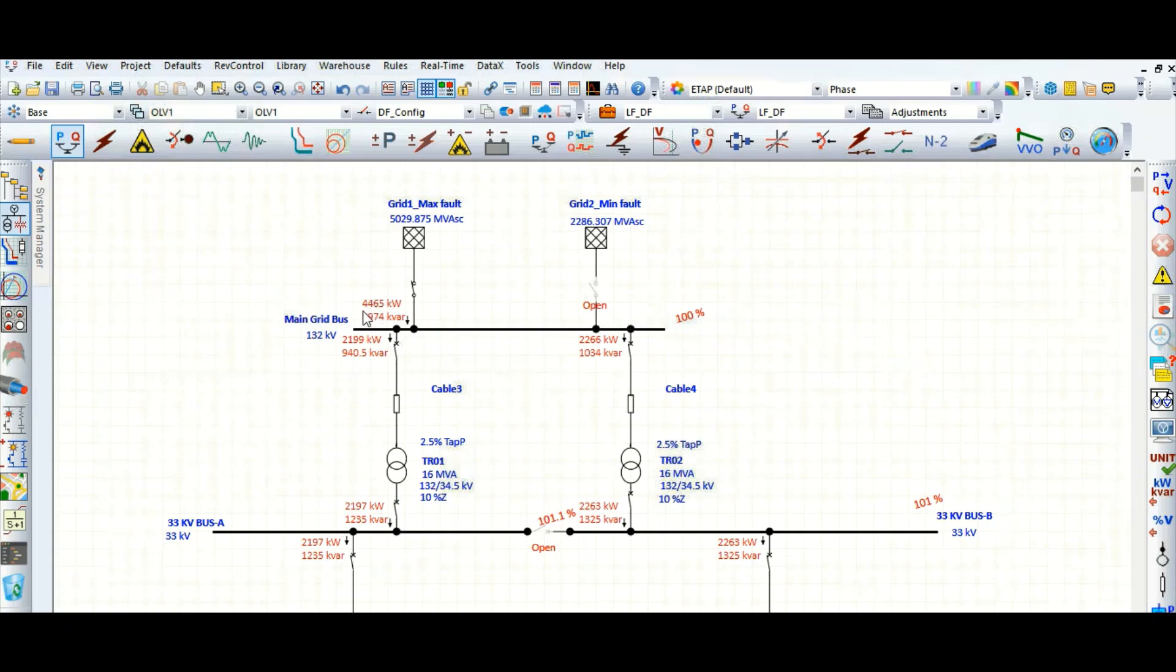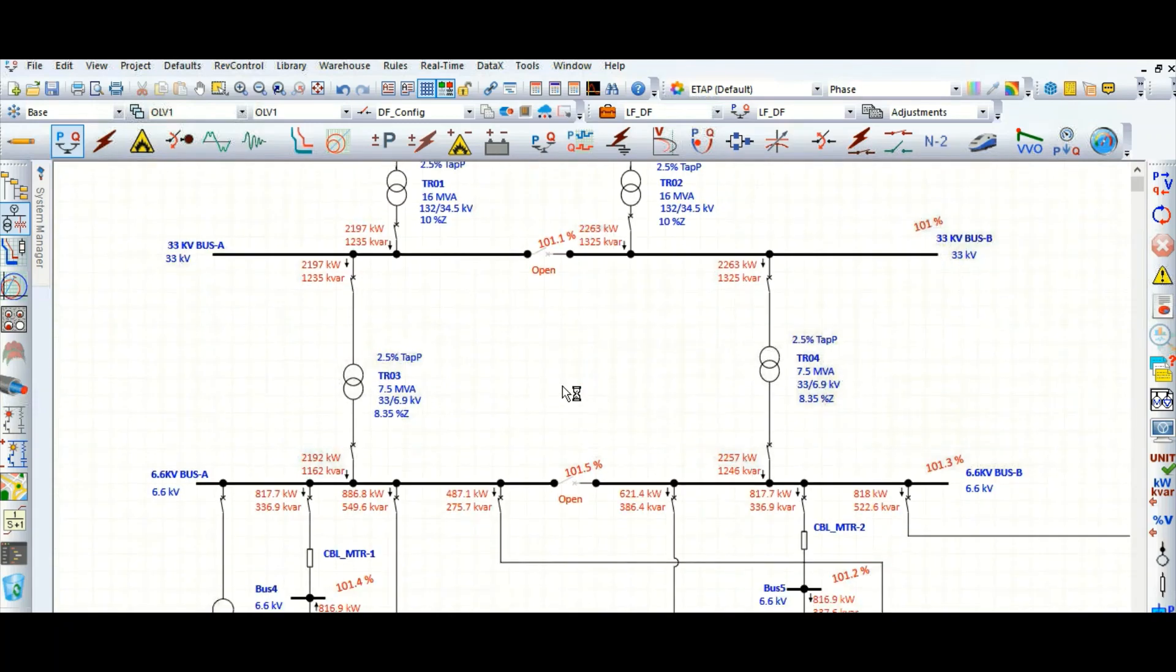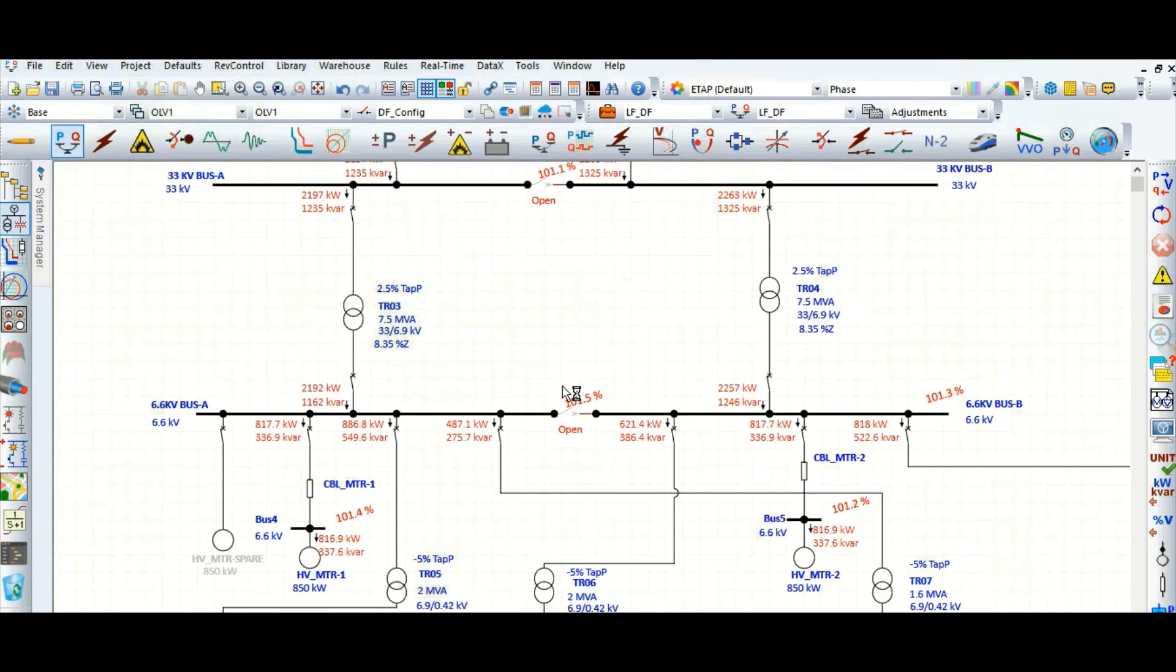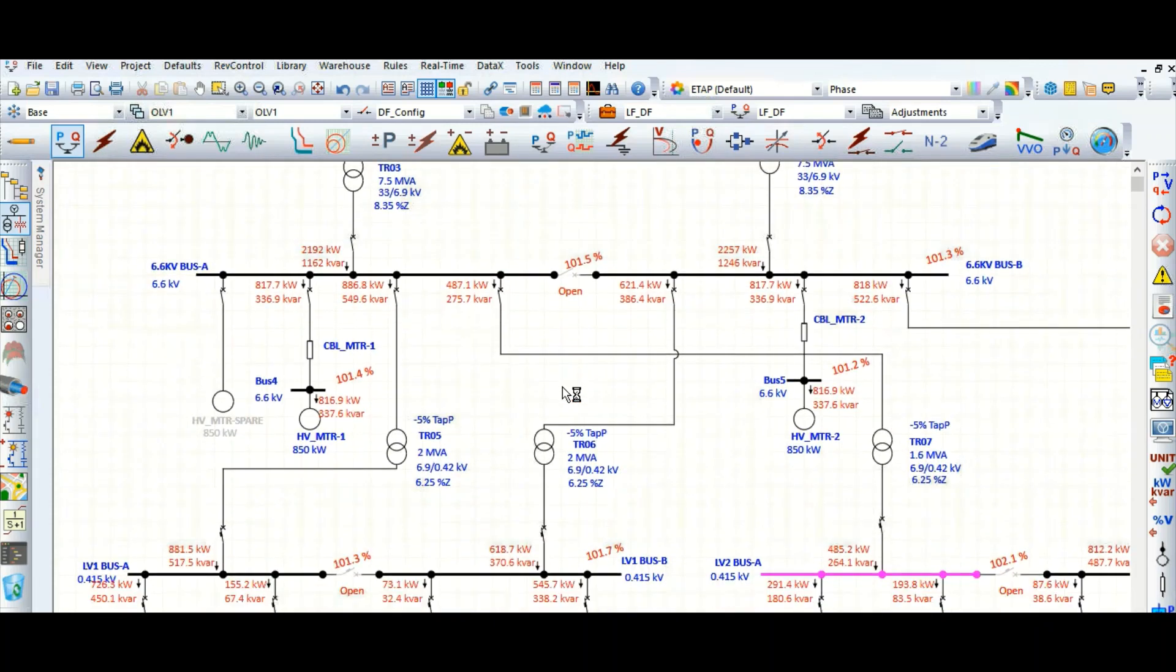So it is 3128. Here, 1539 kilowatt. Let's once again run this load flow. You can see 4465 kilowatt, 2197 kilowatt. So in this way you can change the load scenario based on the actual condition.